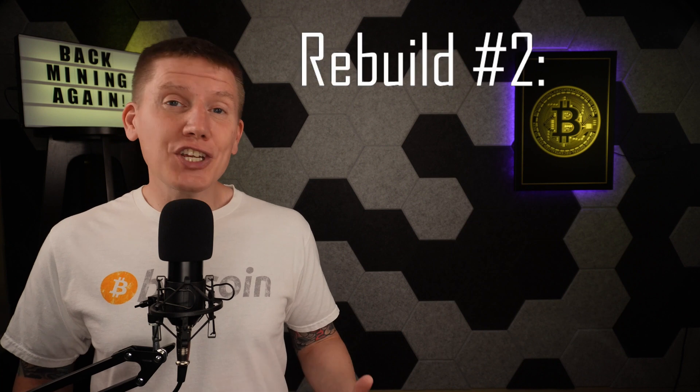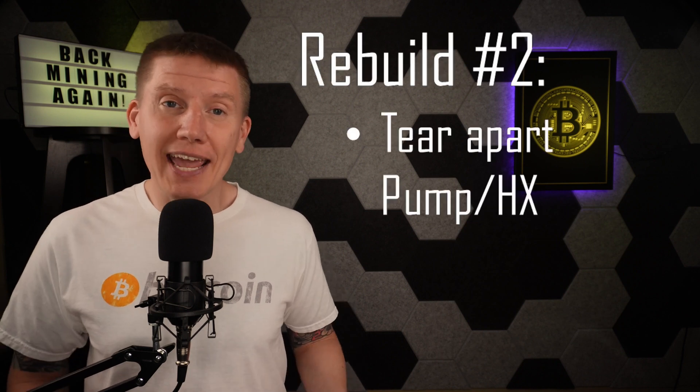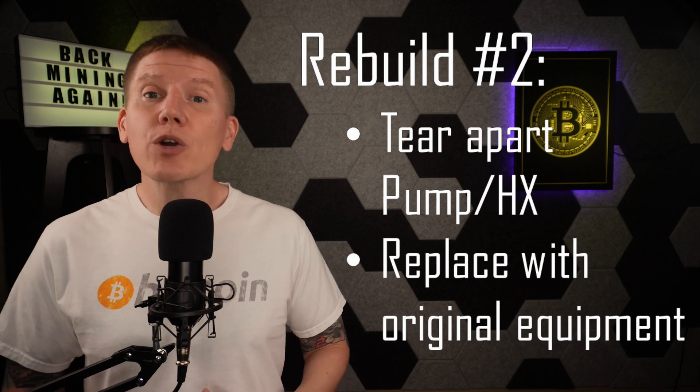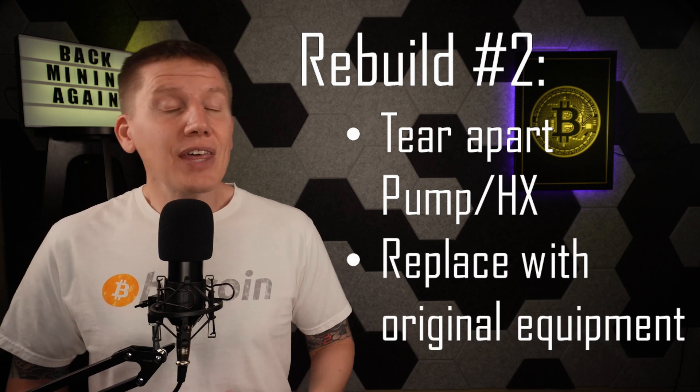At the end of that video, I was thinking the cause of my overheating was the difference in heat exchanger design between my setup and the DCX system. I had made the decision to tear apart the BitPod tank, replacing the pump and heat exchanger with equipment from my original design that worked with my custom-built dry cooler. I wasn't really excited about this decision — DCX builds these systems so they will not leak, and I was worried I wouldn't be able to rebuild without having leak problems — but at the time it seemed like the right call.